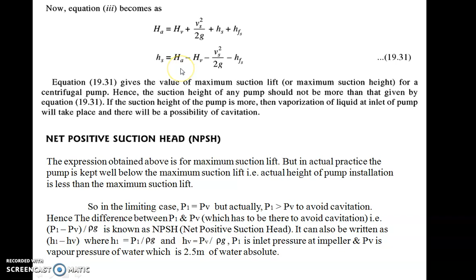So you know NPSH is calculated by using a formula. If you remember the formula for NPSH, the general formula for maximum height was Ha minus Hv minus Vs square by 2g minus Hfs. Hs is the maximum height, so the same formula we are going to use for calculating Hs. So Hs will come to this side: NPSH minimum is equal to Ha minus Hv minus Hs maximum minus Hfs. So Hs maximum will be equal to Ha minus Hv minus Hfs minus NPSH minimum. This is the formula for maximum suction lift. That is, Hs maximum will be equal to 10.193 minus 0.305 minus 0.2 minus 3.036. So it will come as 6.652 meter.